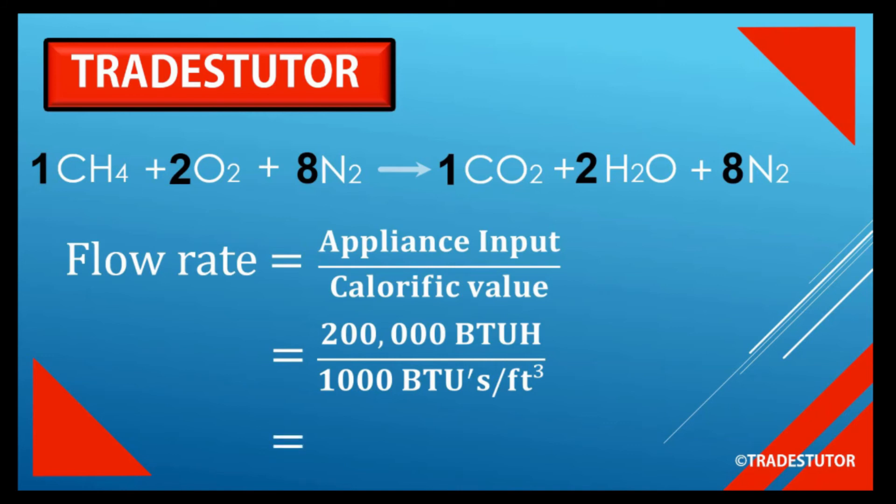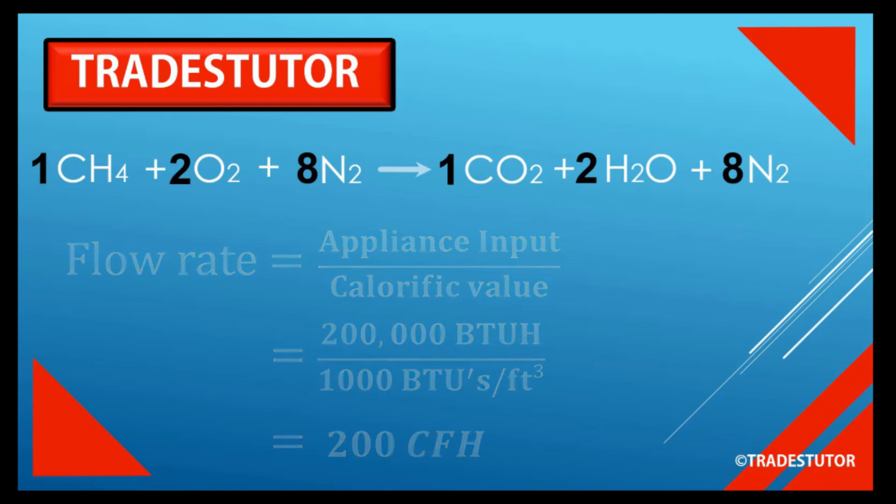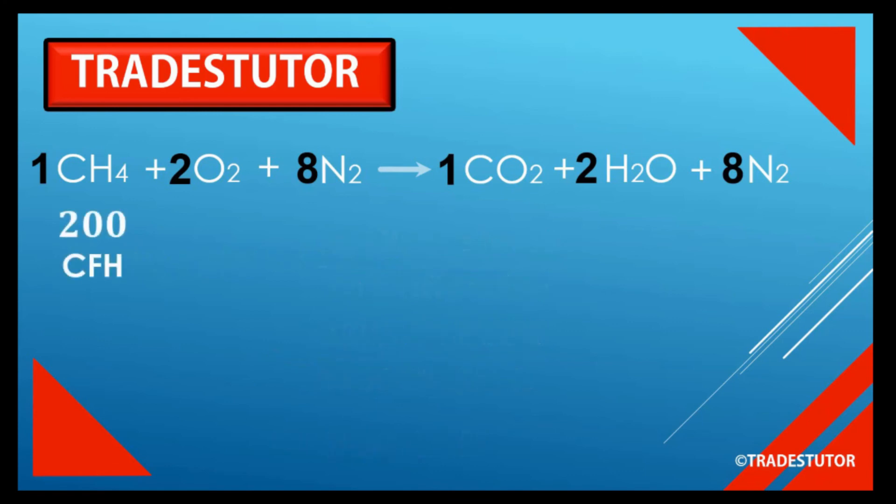What we get is 200 cubic feet per hour. We're going to follow the same ratio when calculating what's coming out the other side. If we have 200 cubic feet of CH4 going in and it's a one-to-one ratio with carbon dioxide, we get 200 cubic feet per hour of CO2. By the same logic, we get twice that for water vapor at 400 cubic feet per hour. For nitrogen, it's 200 times 8, or 1,600 cubic feet per hour. That's it. That's how you figure out the products of combustion.